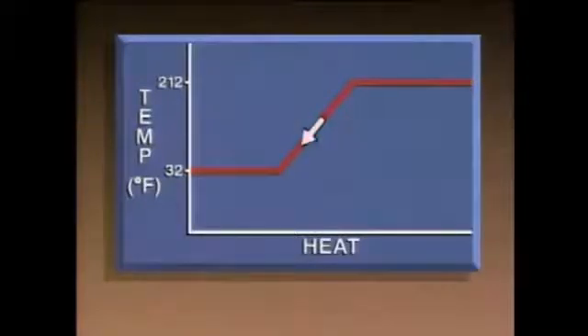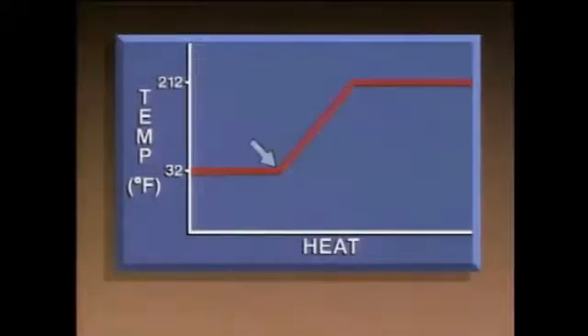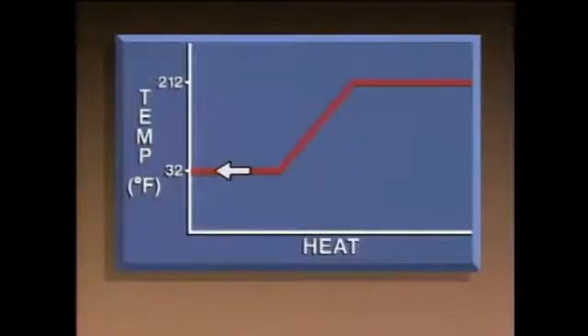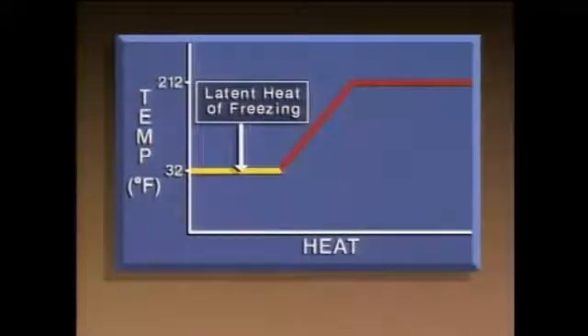When heat is removed from water, there is a sensible heat transfer and the water temperature drops until it reaches 32 degrees. At that point, any heat removed is latent heat, so the temperature remains at 32 degrees. This line represents the latent heat of freezing — the amount of heat that has to be removed from a substance to freeze it without producing a change in temperature or pressure.